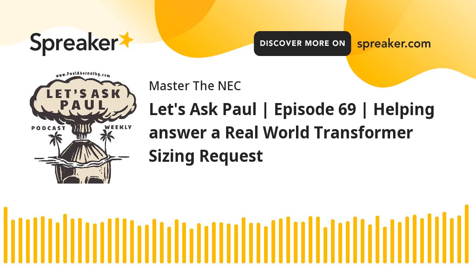All right, so I want to go to 310.16 in this case. Again, all terminals are 75 degrees C, all insulation rated 75 degrees C or greater. I'm going to look for a conductor that's going to handle the 78 amps under 75 degrees C. So I'm going to go down, and it looks like it'd be a 4 gauge. This 4 gauge, again copper, is going to handle 85 amps. Okay, perfectly fine. So from my disconnect down to my HVAC unit, it's going to be a 4 gauge.